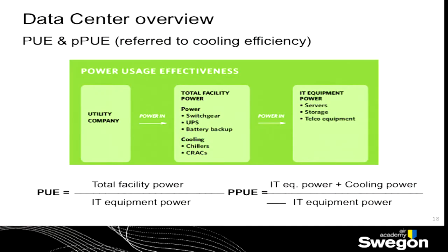We have already spoken a lot about PUE. What I want to introduce is just a definition of partial PUE. It is the PUE connected only to one kind of energy in the building. If you consider the energy introduced in the building for cooling, and you sum it to the IT equipment power, you obtain the partial PUE. So it's a factor that is different from the PUE.